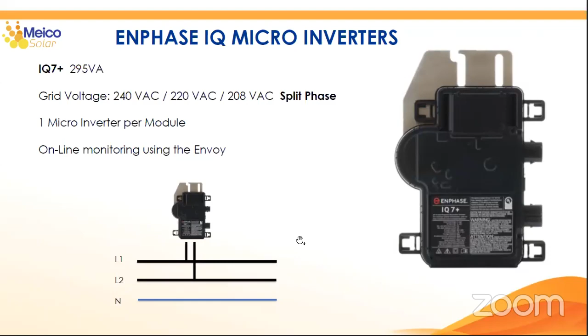So let's see the main advantages of using a microinverter. You're wondering why I would put one microinverter per module if I can make arrangements of 10 modules or 4 modules with other microinverters. The answer is this one. We have the same solution, the same conditions in the left side than in the right side, okay? In the left side, imagine we're having a string inverter connected to these modules. In the right side, you will have one microinverter per module. So one module has a scratch, one other is absolutely and this one has hotspots, okay? So we have modules that are working 100% and others that are working with lower efficiency, okay?